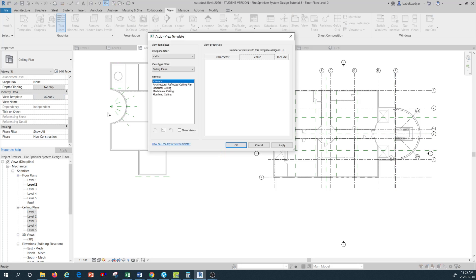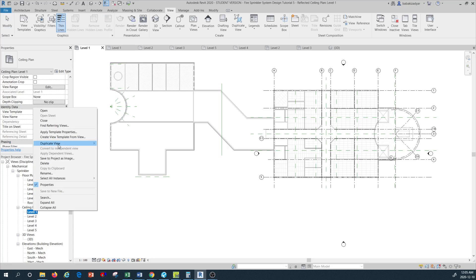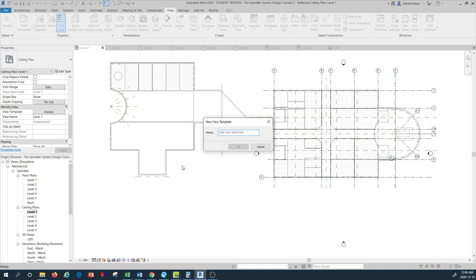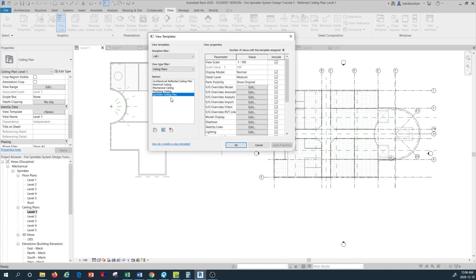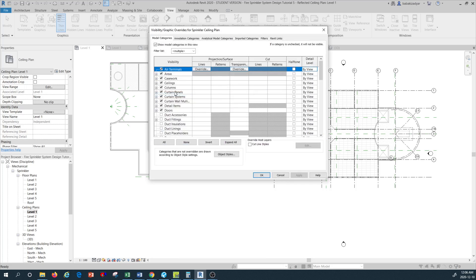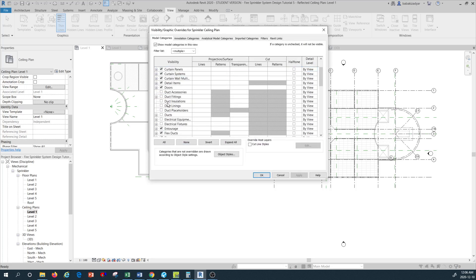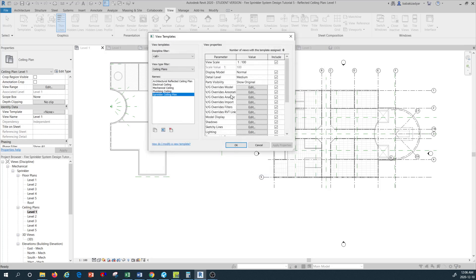We want to apply the sprinkler template to the ceiling plans as well. We don't have a sprinkler template yet in the ceiling plan, so I go to Level 1 of the ceiling plan, right-click, and press 'Create View Template from View.' I'll name it 'Sprinkler Ceiling Plan' and hit Enter. Once this opens, I go to VG and use the same customization — I don't want to see any ductwork. For the sake of this tutorial I won't make other changes, so I press OK.